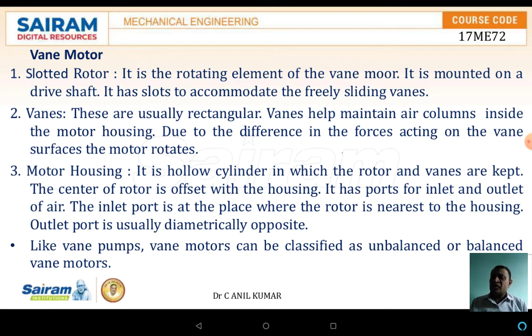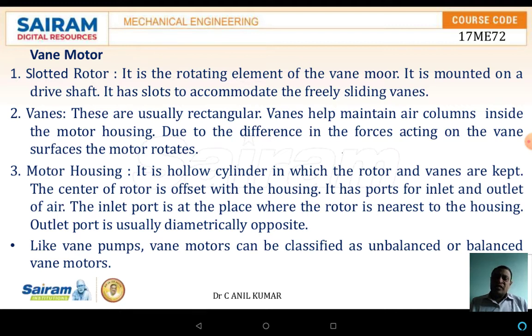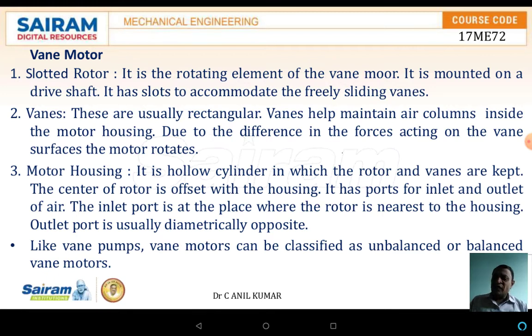The vane motor consists of the slotted rotor, vane motor housings. The slotted rotor is the rotor consisting of slots where the vanes are placed. These vanes are accommodated in such a way that they can move freely — they are sliding vanes. The vanes are usually rectangular.